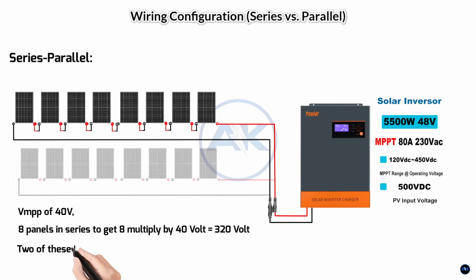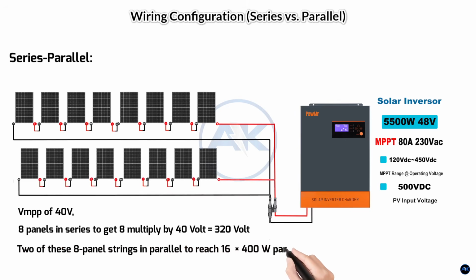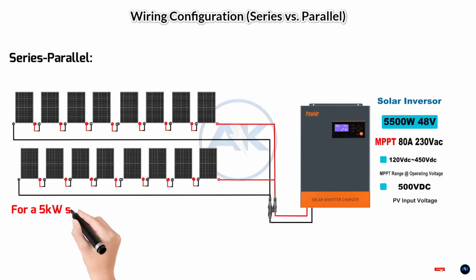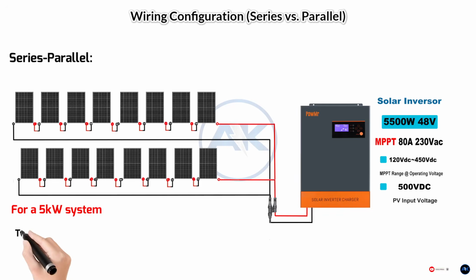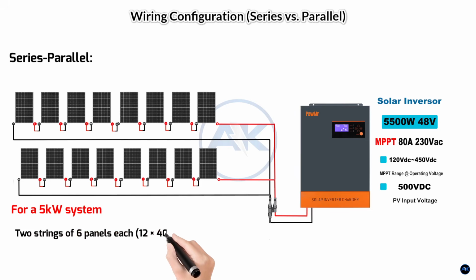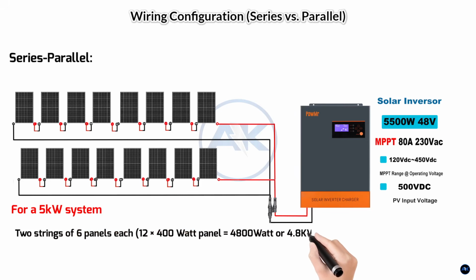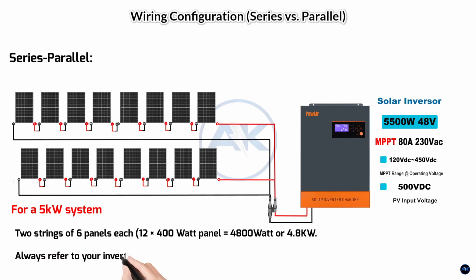Then, you'd have 2 of these 8 panel strings in parallel to reach 16 panels multiplied by 400 watt panels equals 6,400 watt total PV array, providing some headroom. Or, for a 5 kilowatt system, you could aim for a slightly smaller array, like 2 strings of 6 panels each. 12 multiplied by 400 watt panels equals 4,800 watt or 4.8 kilowatt. Always refer to your inverter's specifications for optimal string sizing.